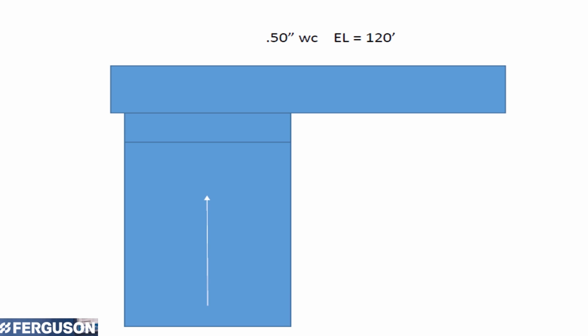So this type of fitting is most common on existing duct systems. And again, as the air comes out of the air handler or furnace, it'll hit the top of the ductwork, it'll recirculate and turbulate, and finally get down the ductwork. And at a 0.5 inch of water column external static pressure, this type of fitting adds to your ductwork 120 feet of equivalent length before you even get out of the equipment.